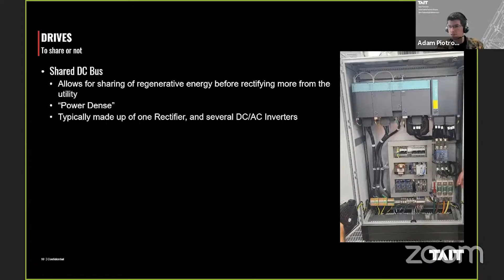So in this cabinet, we actually have three drives. We have these first two drives, which are 85 amp drives, followed by a 45 amp drive. If one motor happens to be regenerating energy, moving with gravity, converting the potential energy stored in gravity to electrical energy because we're lowering that load, it can push it back to the DC bus. And if one of the other drives is lifting a load, we can essentially recycle that energy before we have to pull more from the utility. It's also fairly power dense because we're not duplicating the rectification stage. That rectification stage only happens once, and these two units on the right side are our rectification stage. So we can make the cabinet fairly power dense. It's typically made up of one rectifier and then several of those DC to AC inverters.